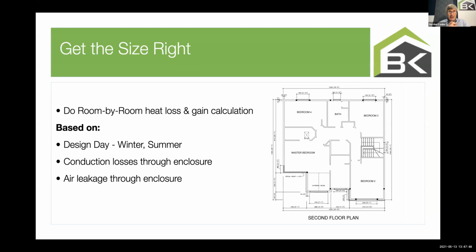So it is about getting the size right, not only at the house level, but at the granular level, at the room size. So I wanted to just show you quickly how to do that. Hopefully you're okay with this. And again, you would choose the design day. You would think about conduction losses through the enclosure of each individual room. You would, in terms of heat loss, think about the air leakage through the enclosure under those various rooms. And of course, you would want to think about the radiant gains through windows.